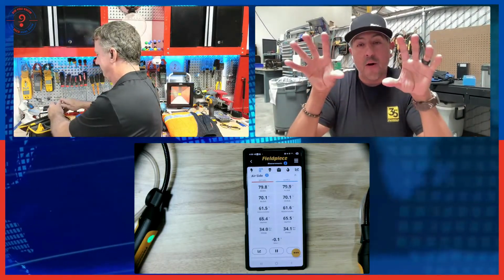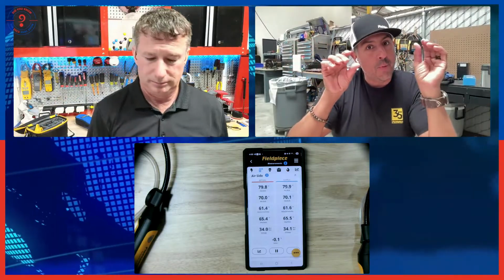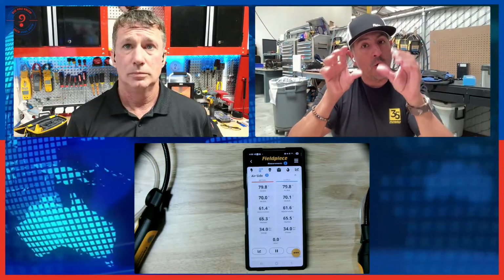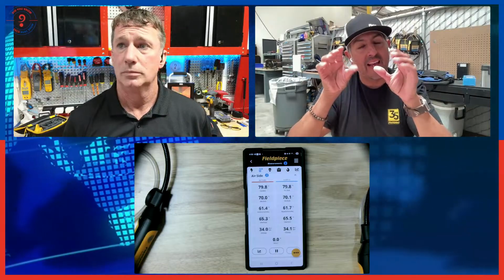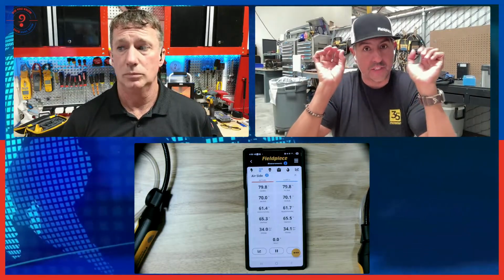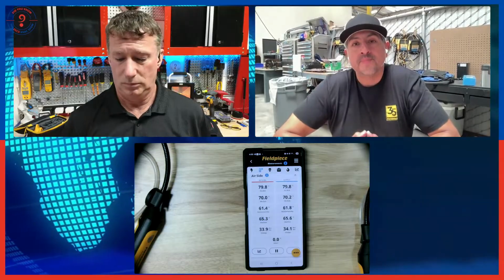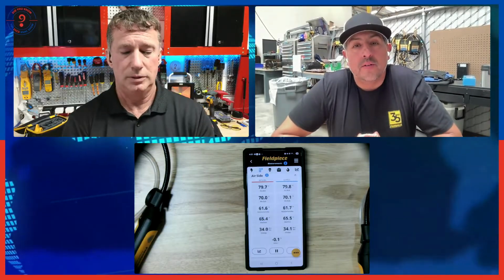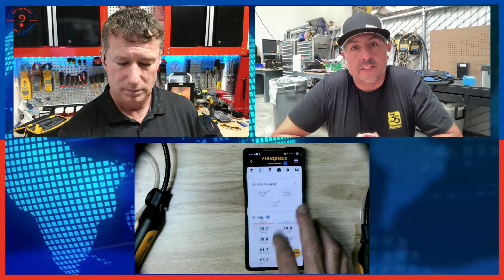For airflow we're going to be looking at static pressures, and with the psychrometers we're going to be looking at heat transfer across that coil, which is key to understanding performance. All right, so now we'll move into the refrigerant side of the system.